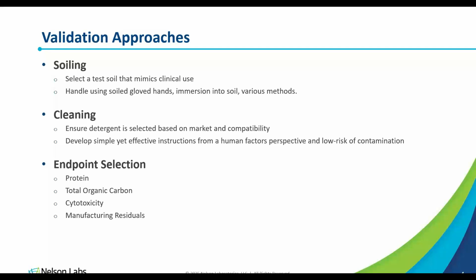When it comes to soiling, the standard approach for soiling a device is to mimic clinical use. What that means is you select a test soil, a contaminant, that mimics the use of the device. As an example, for a reusable device such as an orthopedic surgical instrument, we would select a test soil that may have some blood and some bone, mimicking what it would see during clinical use.